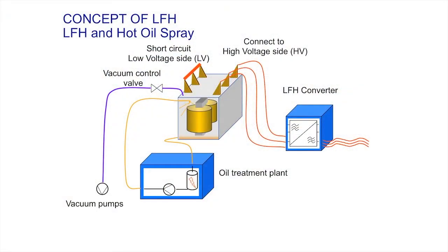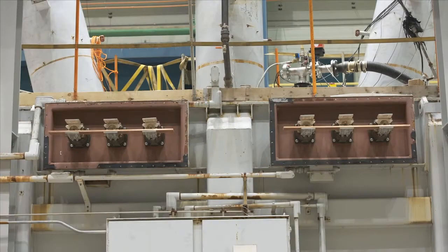The cables for the external voltage measuring can be connected to the high voltage bushings if the power cables will be extended or the transformer has an extremely low resistance. These external voltage measurements will then compensate for the resistance in the power cables. The low voltage windings should be short-circuited. The connection must be able to hold the nominal current of the LV side of the transformer.